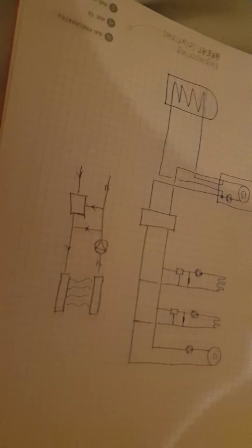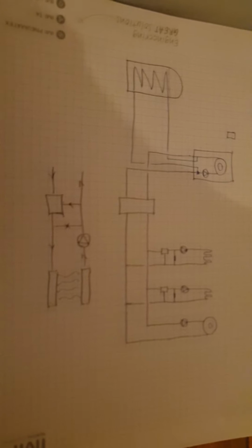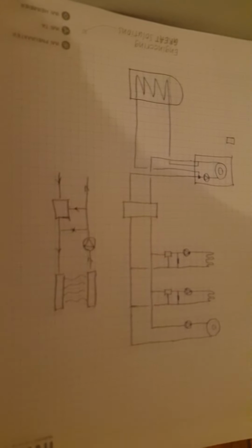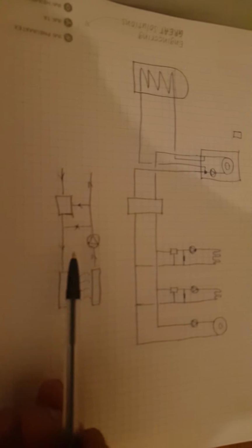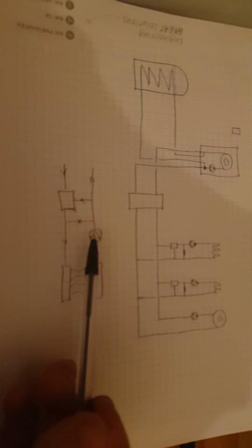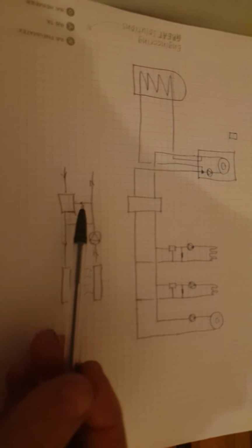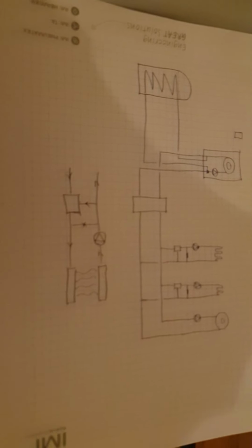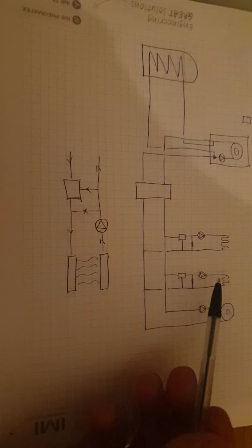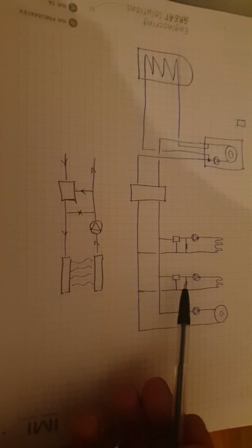But now Adam's on Heat Geek has done a video explaining an alternative to close coupled T's. And it seems that people are thinking it is close coupled T's. What he's in fact done is used the Vstream design. He's got the pump on the return, which confuses issues, and there's a little bit of a dog leg in this pipe work here because he couldn't fit it on his installation. But basically all he's done is used the Vstream fixed rate bypass system rather than using a close coupled T.